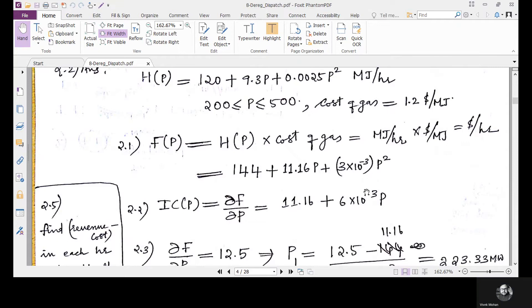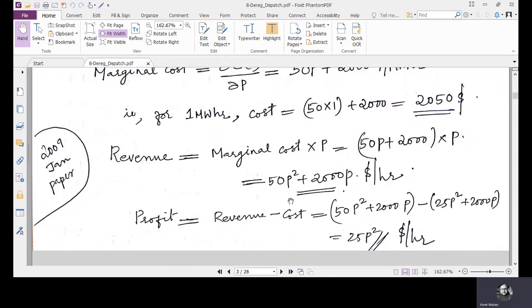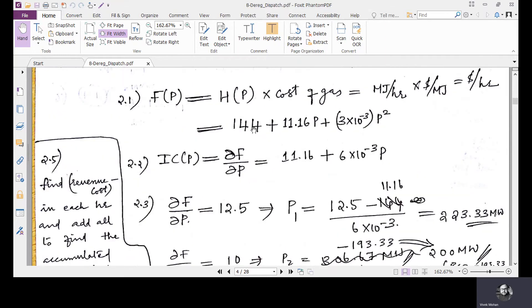In part two, derive the generator incremental cost or marginal cost function IC(p). Taking the derivative of F(p) with respect to p gives the energy cost in dollars per megawatt hour. Since F(p) = 144 + 11.16p + 3×10⁻³p², the incremental cost is dF/dp = 11.16 + 6×10⁻³p dollars per megawatt hour.